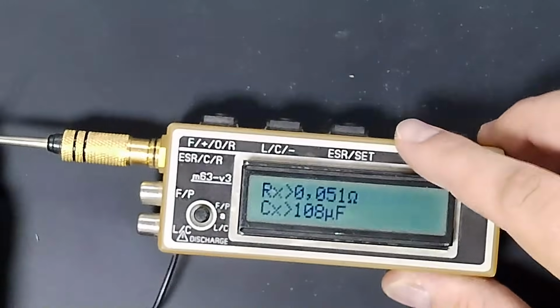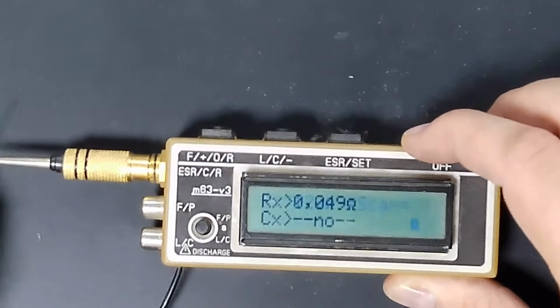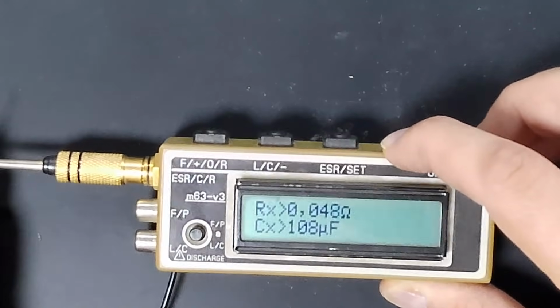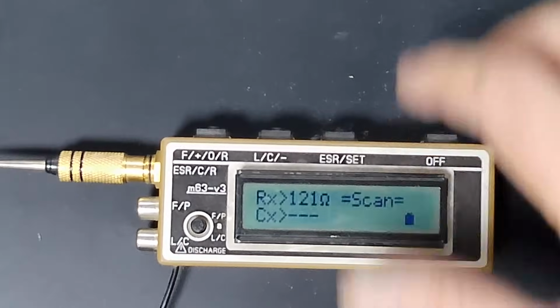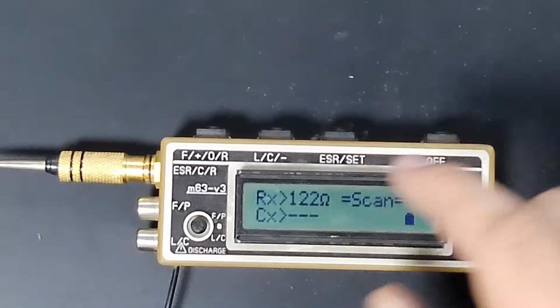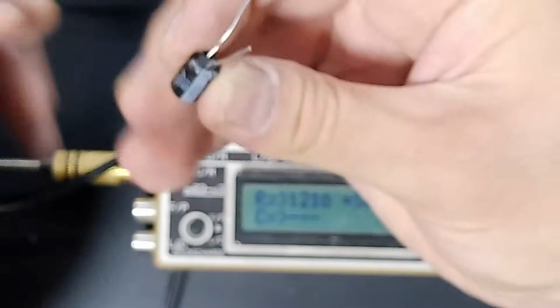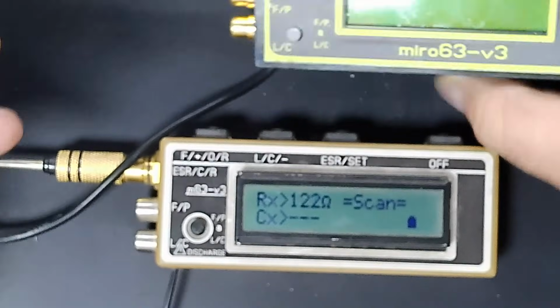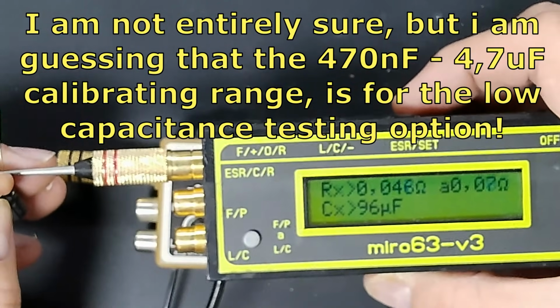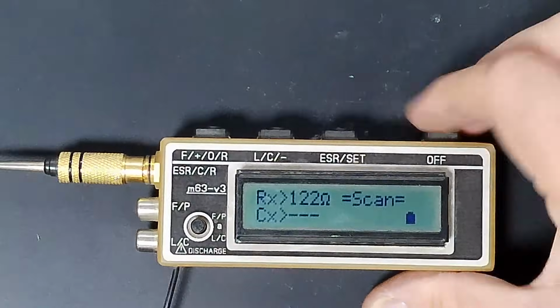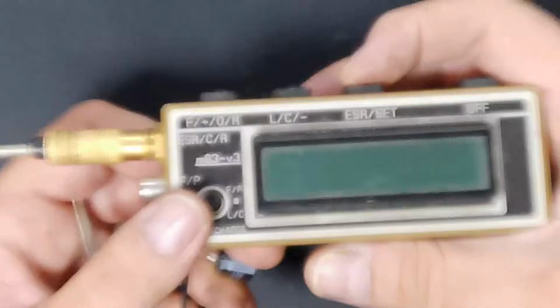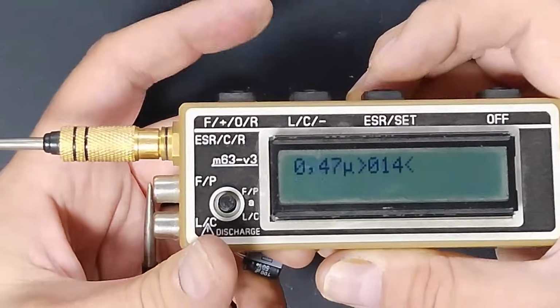So what about now? Still over 100 microfarads. Let's try and calibrate it with this capacitor—maybe it needs calibrating on this range. As I said, 96 microfarads, this is what it should read. So turn it off, press and hold set, then minus, then release.